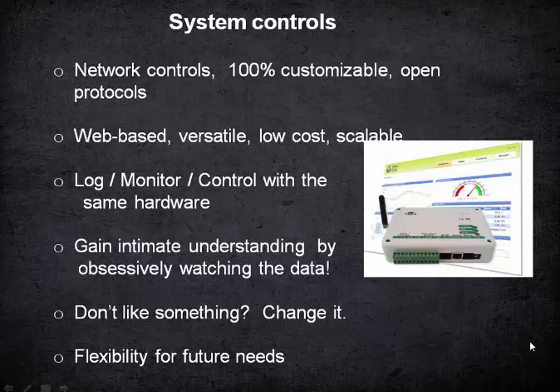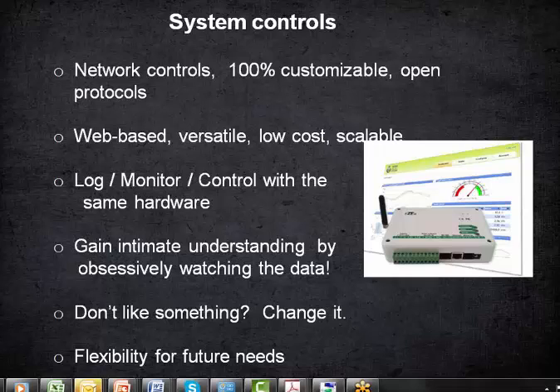And then when you go beyond that main controller, you choose which open protocol network you want to use. Well, you don't really choose, because there's just 2 networks: microLAN and Modbus. Modbus is an open standard protocol, so you can go buy peripheral devices, input-output devices—we have some, but there's other stuff on the market people could choose to use also. So you're not getting married to any particular proprietary system with stuff like this, and we like that.